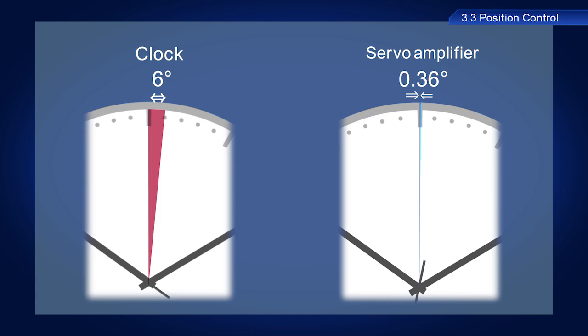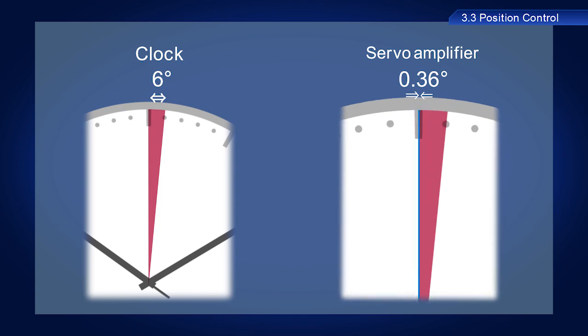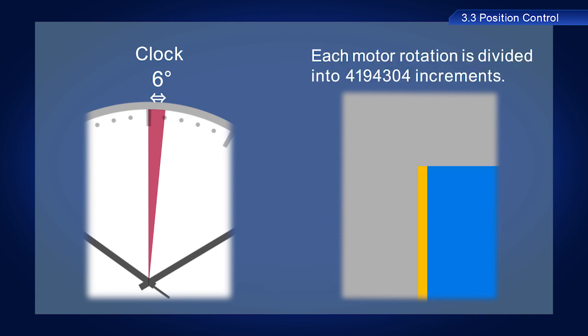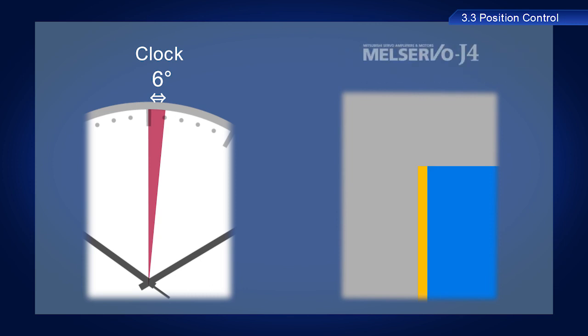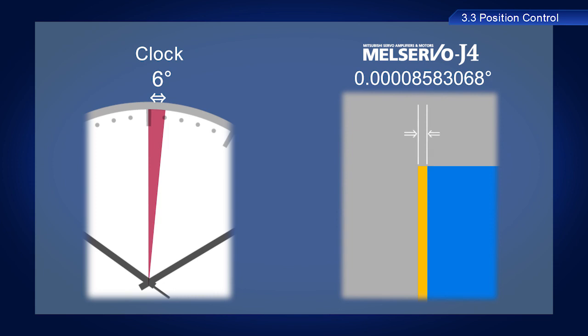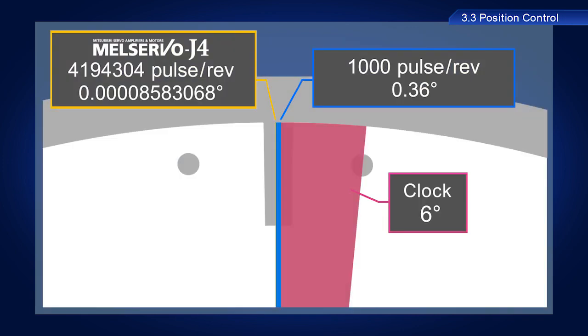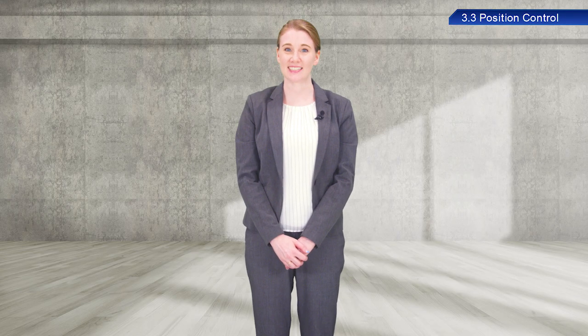In this example, the servo amplifier moves 0.36 degree for each increment, which is obviously a much higher resolution than a clock. The resolution of the Mitsubishi Electric MELSERVO-J4 is 4,194,304 pulses per revolution. This means that 360 degrees of rotation is divided into 4,194,304 increments. This means that this extremely high-precision device causes a mere 0.00008583068 degree of movement with each pulse. OK, let's go back and finish the setting.